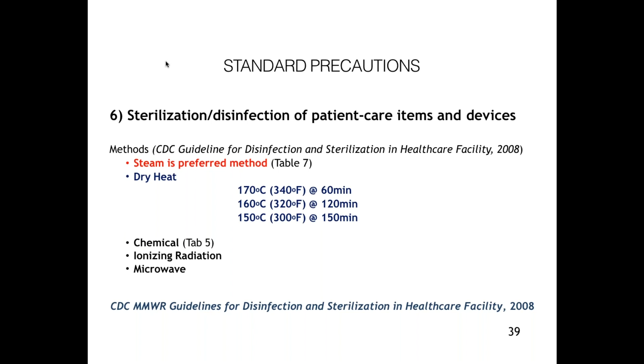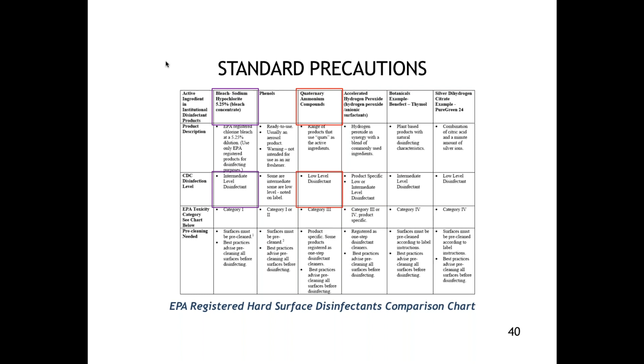All right. So when it comes to using disinfectants, the big question always becomes bleach versus quaternary ammoniums. And what you need to know is that bleach at 5.25% is an intermediate level disinfectant, which means you could use it for semi-critical items, but critical items and semi-critical items will not be addressed with a quaternary ammonium compound. It just won't, because that's considered low level. That's the purpose of this slide.